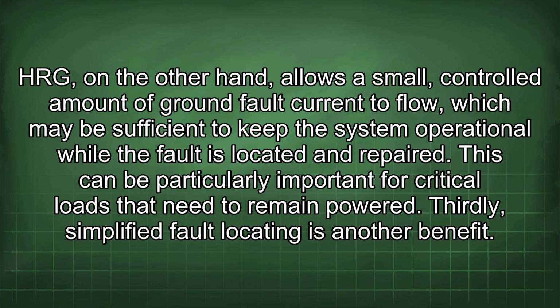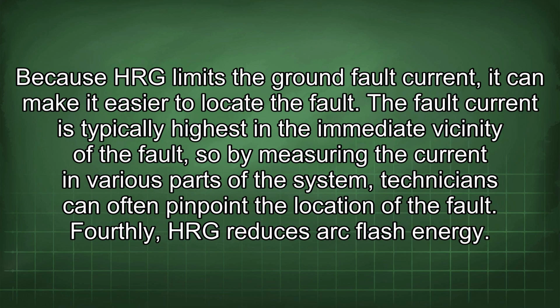HRG, on the other hand, allows a small, controlled amount of ground fault current to flow, which may be sufficient to keep the system operational while the fault is located and repaired. This can be particularly important for critical loads that need to remain powered. Thirdly, simplified fault locating is another benefit. Because HRG limits the ground fault current, it can make it easier to locate the fault. The fault current is typically highest in the immediate vicinity of the fault, so by measuring the current in various parts of the system, technicians can often pinpoint the location of the fault.